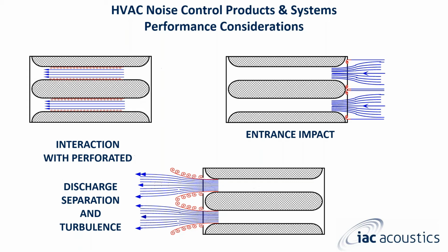Now, I will say this. Some of the competition on the discharge end of the silencer, it tails off. So air follows the path of what? Path of least resistance. Air will bounce off the side of the silencer and or ductwork as it leaves the silencer, and it will then start to rumble. So one of the things I will say is that with our silencers, not only do we have some of the best performance out there for insertion loss, but we also have the most minimal impact of self-noise being emitted back into the system.